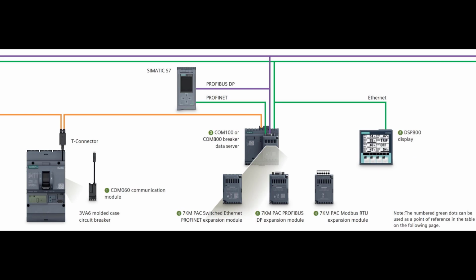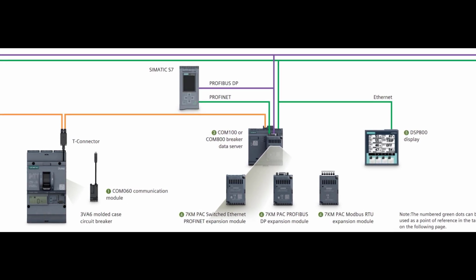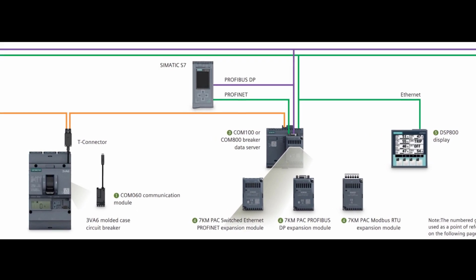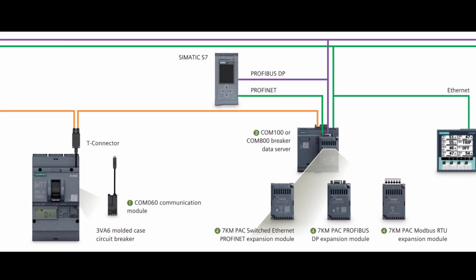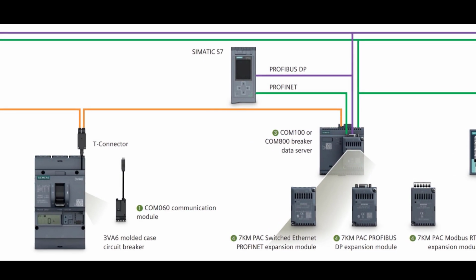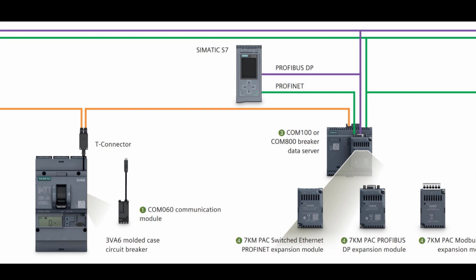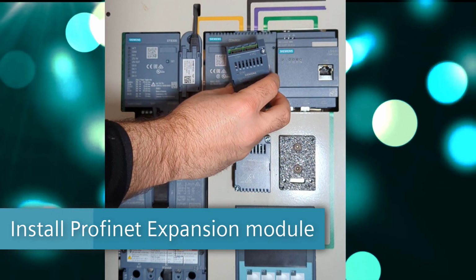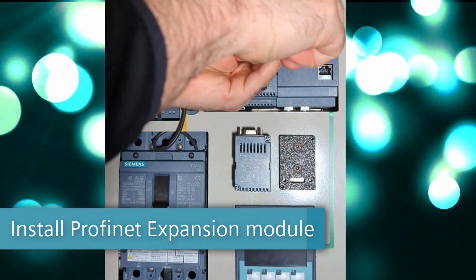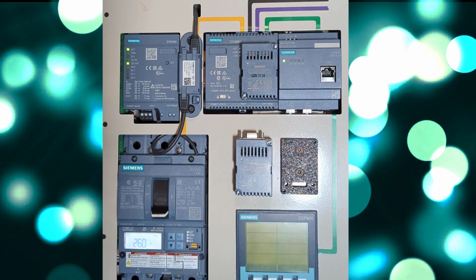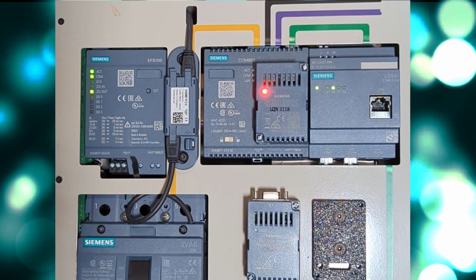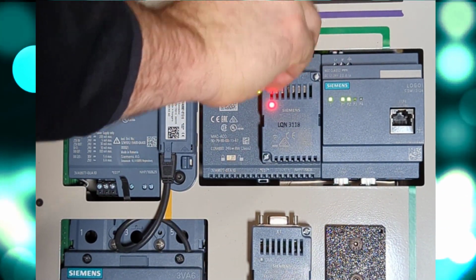Today's demonstration will use many of the parts that you see here in front of you, including the SIMATIC S7-1500 PLC, a COM800 breaker data server, switched Ethernet Profinet expansion module, COM60 communication module, as well as a 3VA molded case circuit breaker, along with a few T connectors to connect the energy components. Let's go ahead and look at the installation process for a Profinet expansion module. In this example, a COM800 in system connected to a 3VA6 is already established and put in place. The expansion module can be screwed into place, and a network connection supplied between the expansion module and the PLC.